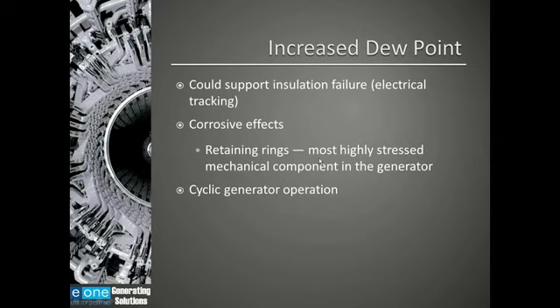What is a good dew point? Most manufacturers will say 0 degrees C. You want to keep your dew point lower than 0 degrees C, with 0 degrees C normally being an alarm point. Hydrogen from bottles or bulk systems usually is very dry, and the hydrogen from a hydrogen generator system is always dry. So where does the moisture come from? In most cases, the moisture in the generator will come out of the seal oil. However, it could come from the cooling water, whether that's from the coolers, a leak in the coolers, or a leak in the stator winding, if it's a water-cooled stator.